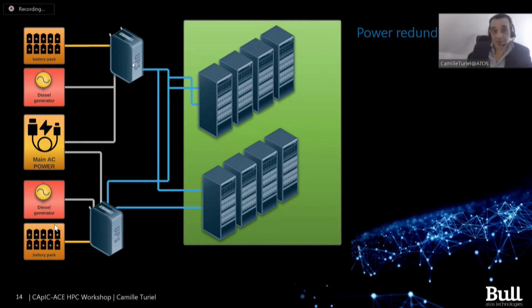So when the power outage occurs, the UPS will act as a buffer. As said previously, it's not meant to last the whole duration of the outage. Not at all, because that would require a gigantic battery park and a gigantic UPS, which isn't something you can realistically handle. Keep in mind that a UPS in a data center is really meant as a power buffer, and that's it. I'd say between a few seconds to a few minutes, but that's it. Don't expect more from a UPS of that power.